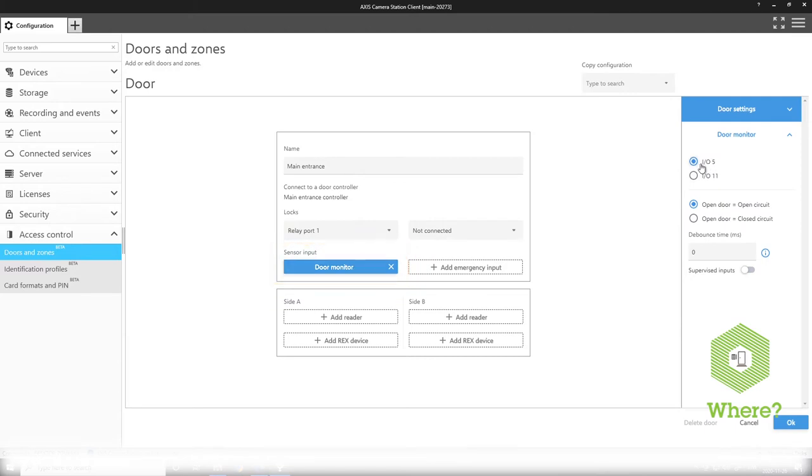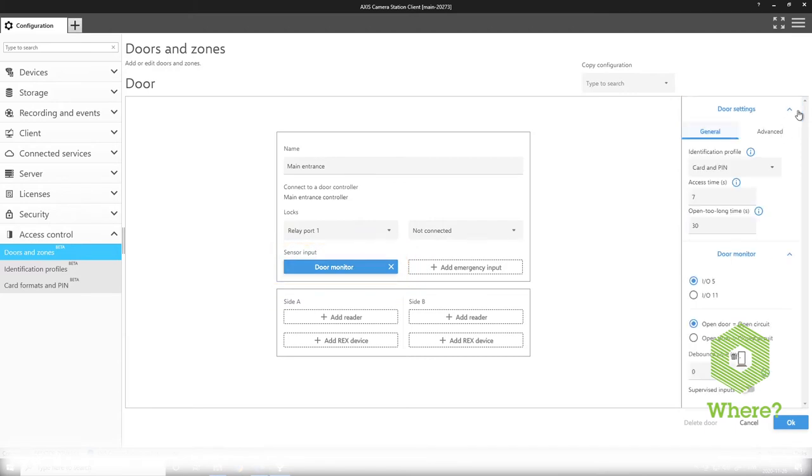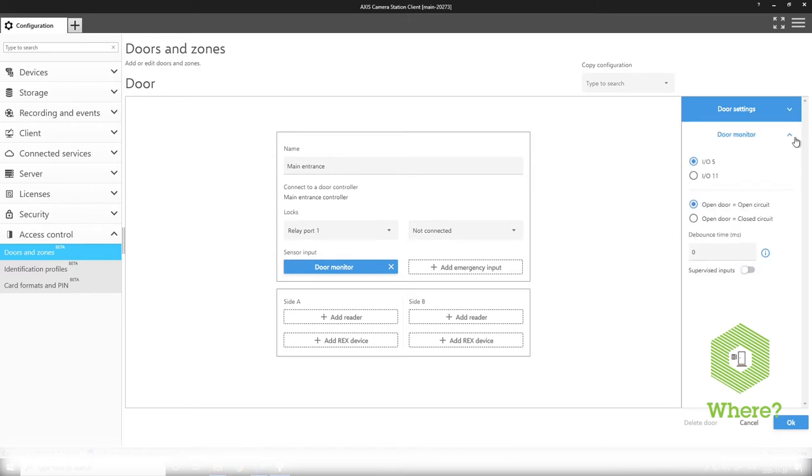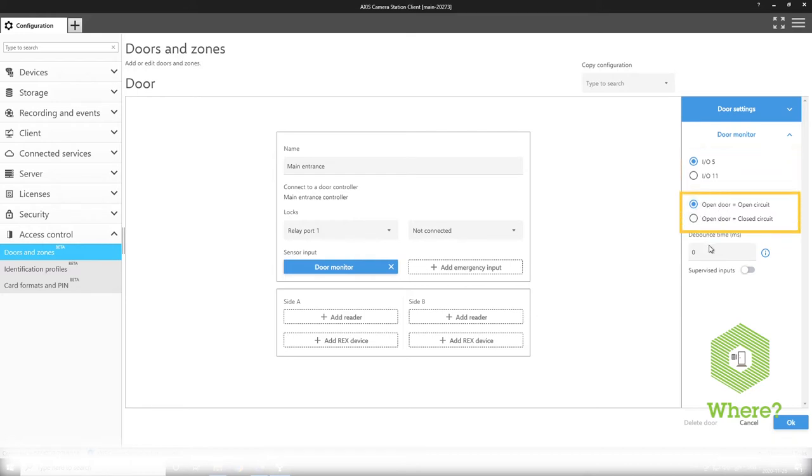Then we can add a door monitor and as you can see here when I add a door monitor I have some selections relevant for the door monitor itself. So the door monitor you select which I.O. to connect it to and also the polarity. You can set a debounce time if you have some issues with jittering on the signal.